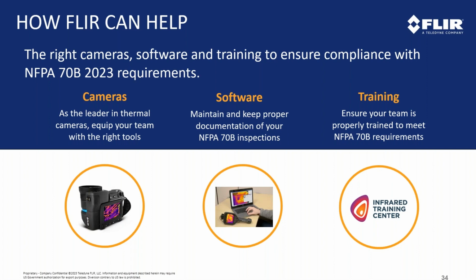And then lastly, just the cameras themselves. Just want to point out this delta T calculation. We're able to perform that on the camera itself, as well as in the software. So you can leverage those tools very effectively to streamline the process, with routing, and get the type of reporting you need for compliance. So these are all different ways that we can help on the NFPA 70B side of things.